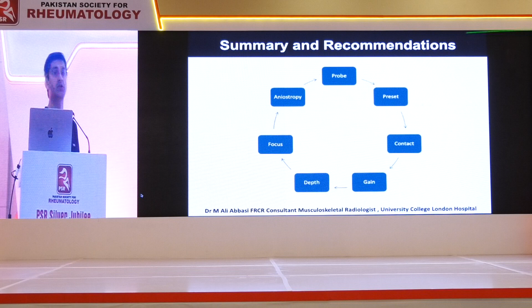Now, on the newer probes, you can actually adjust the frequency, so you don't have to necessarily go down. So on an 18 megahertz, it will have 3 settings. It'll have when the probe is operating at very high frequency, so around about 18, but you can turn it right the way down to about 12. So actually, you might not necessarily need to change the probe, but the principle is the same. Change the frequency of the probe, okay? And then go through this process again. And that's why this is a cycle. It just goes round and round and round.